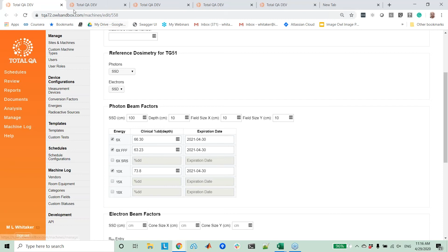The next level of setup is when you're setting up your various measurement devices. These are the ion chambers and the electrometers that you're going to use with your TG51 measurements. On this page, as Ariel mentioned, we just rolled out some changes recently, and this is where all your measurement devices live. In a normal account, you would have a lot of daily QA devices like DQA3s and SI QA beam checkers. If you're connected up to PIPS Pro or you're importing for MPC, that lives here. You can filter down that view. But in this case, we've basically got a couple of chambers and an electrometer here.